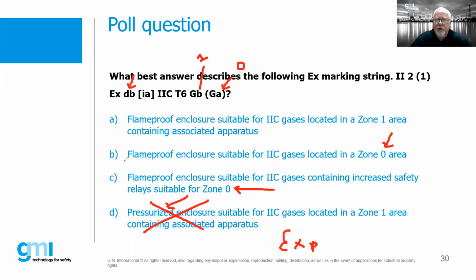So the other issues: the flame-proof enclosure is suitable for 2C gases located in a zone 0 area. No, because this box is not suitable for zone 0. It would have to be marked Ga, and we don't have that. Flame-proof enclosure containing increased safety relay suitable for zone 0. No, that's also not correct.